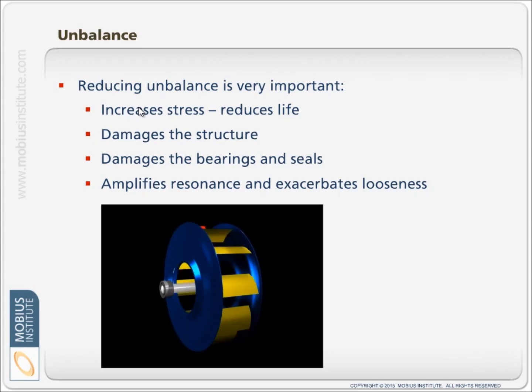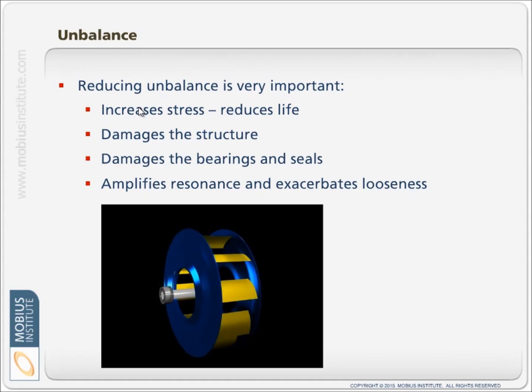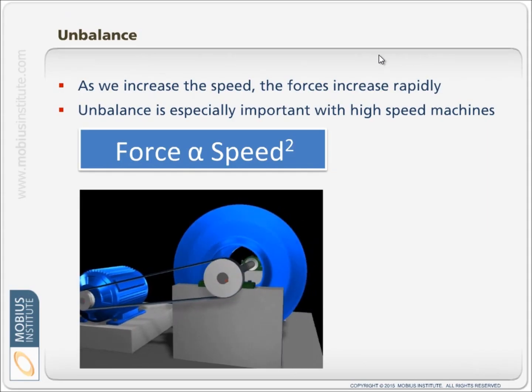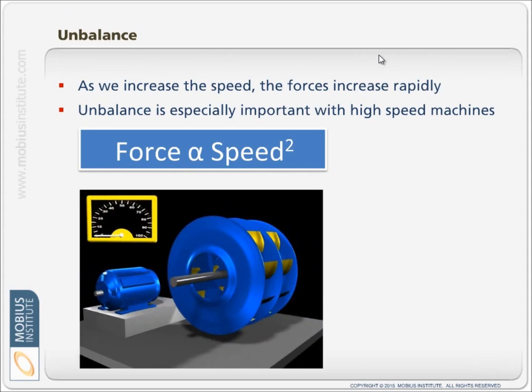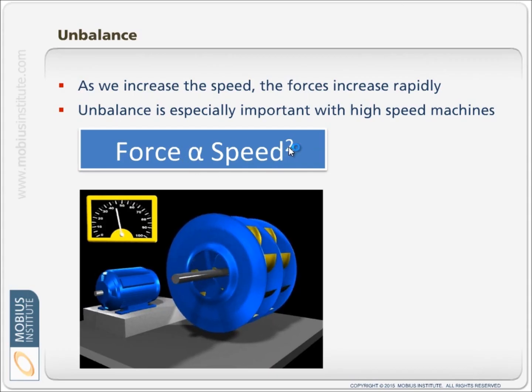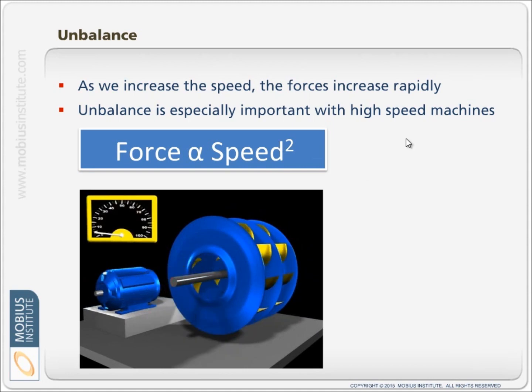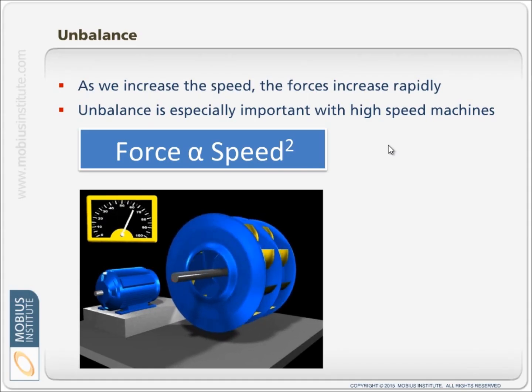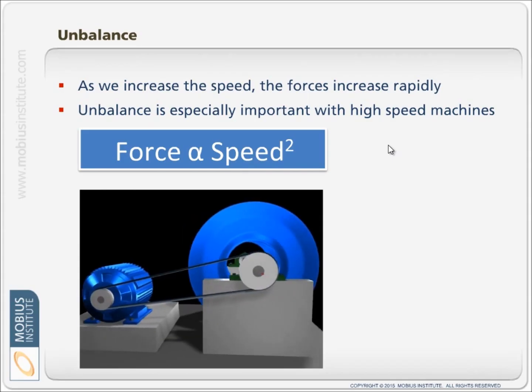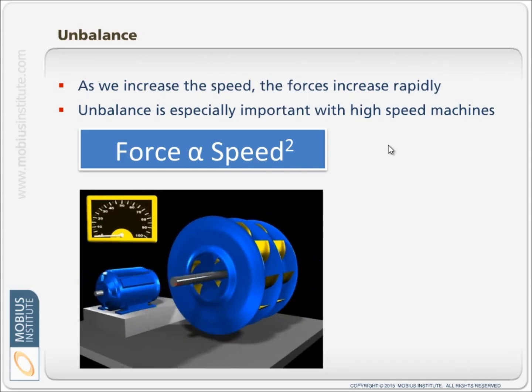Similarly, if there is any looseness, then unbalance drives that looseness — if it's loose, we get more motion when there's more unbalanced vibration. Another key thing about unbalance is that the forces generated are proportional to the speed squared. So if we double the speed, we get four times the amount of force or motion, as this animation shows. Therefore, for a high-speed machine, unbalance is extremely important and it is critical to minimize it as much as possible.